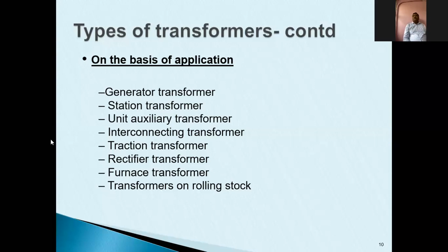I have to take care of the overfluxing or underfluxing of my core. It should not go beyond the hysteresis curve. Otherwise, my core will get saturated. So each and every application will have an implication on the design of the transformer. We have to consider all these facts while ordering or buying a new transformer, or while making the specifications of the transformer, according to where I am going to use it.